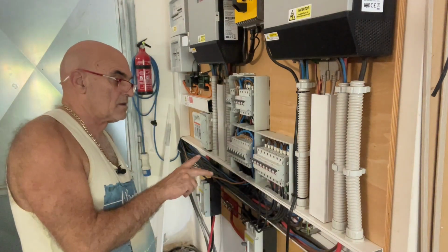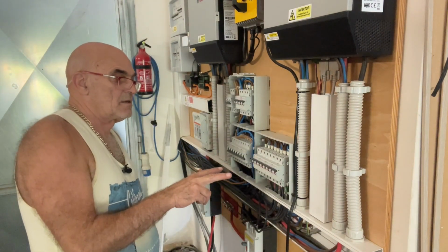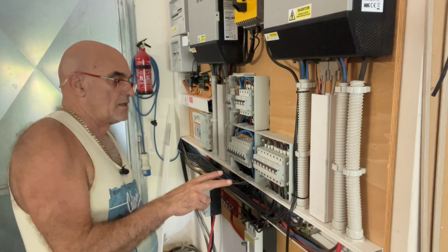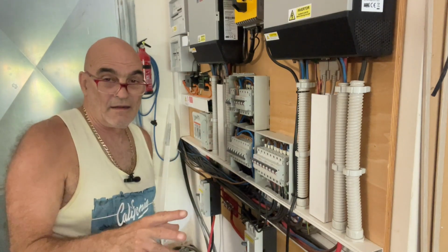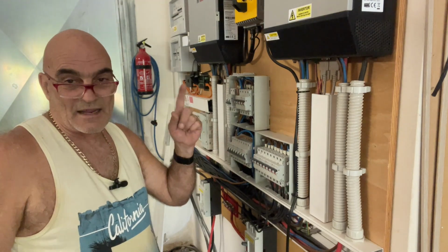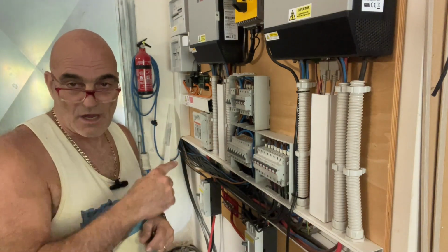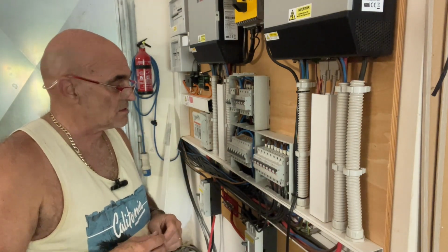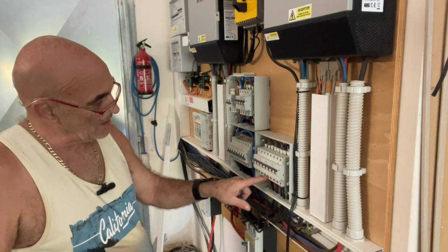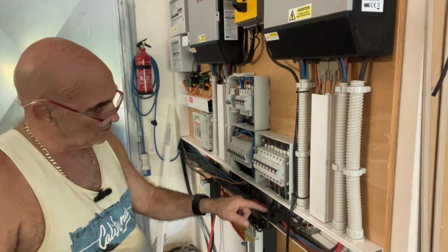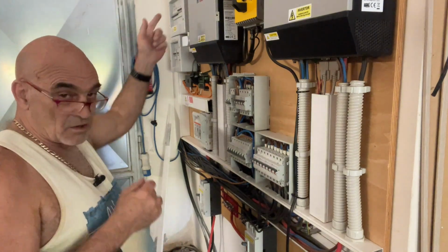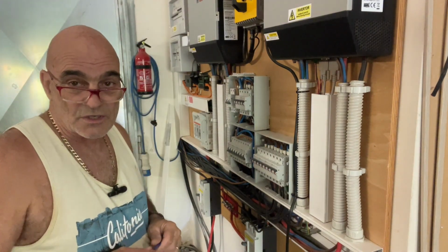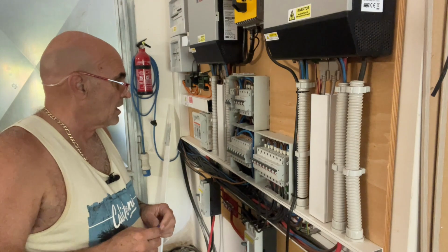I've identified the 4 strings that I need. Now I need to go up on the roof again and disconnect all the connectors so there's no power coming in from the solar panels. Then I need to disconnect the strings I'm not using and pull the cables back so I can pull them up and out through all the conduiting, to reuse them later.